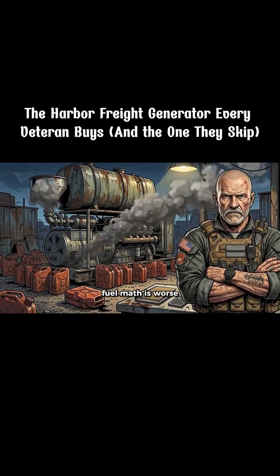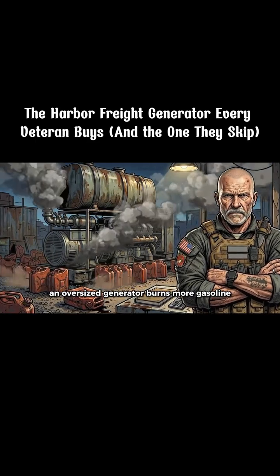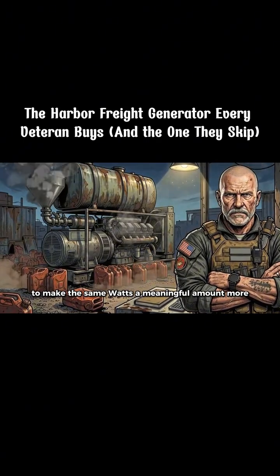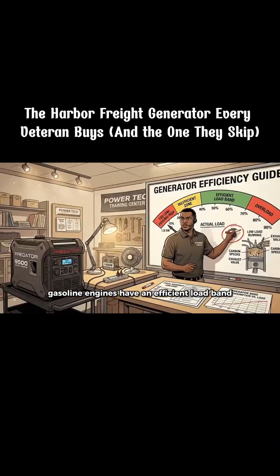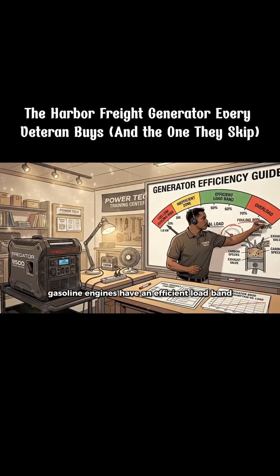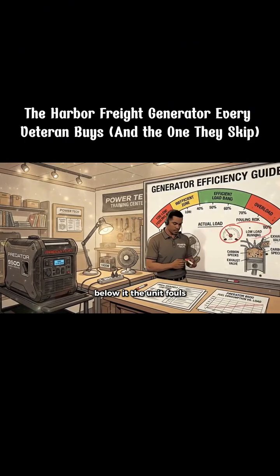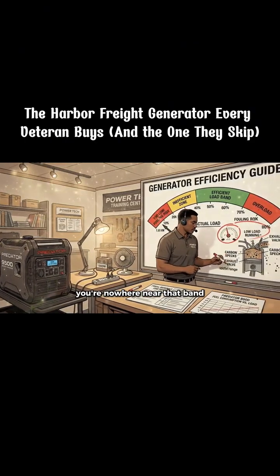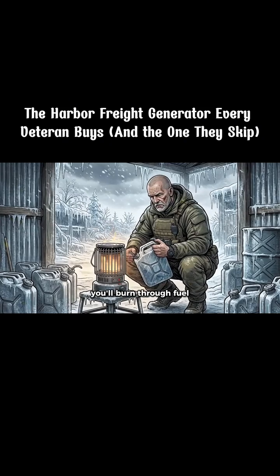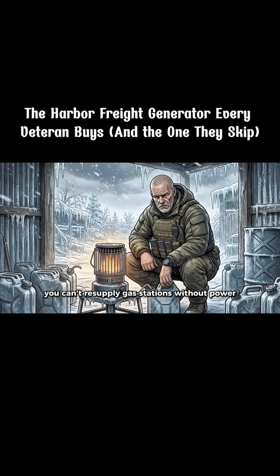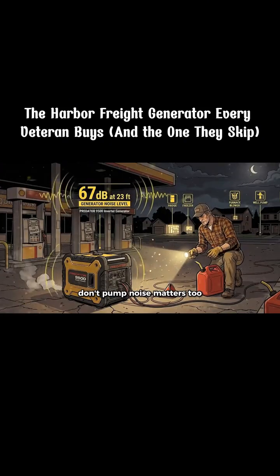Fuel math is worse. An oversized generator burns more gasoline to make the same watts, a meaningful amount more. Gasoline engines have an efficient load band. Below it, the unit fouls. You're nowhere near that band. During a 3-day ice storm, you'll burn through fuel you can't resupply. Gas stations without power don't pump.